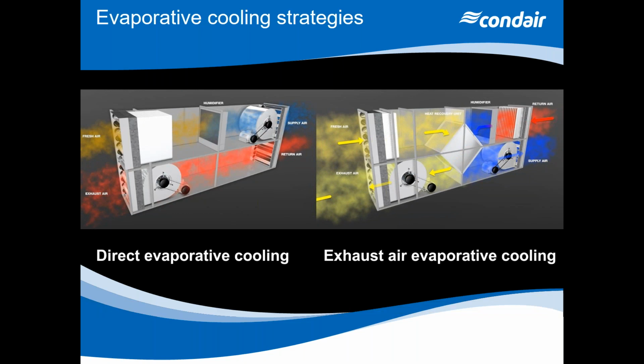So here you can see the evaporative cooling strategies. We mentioned that we've got a change in temperature. Whenever we've got a change in temperature, there are ways that we can utilize that. And in this slide, we can see that there are two ways that we can do it. We can do it either directly, or we can do it with exhaust air evaporative cooling. So when we're doing direct evaporative cooling, all we're doing is taking the fresh air and running it through the filter and then over a humidifier. We're cooling the air, it's evaporatively cooling, and then we send that into the space. And that's pretty straightforward. We then send that humidified air straight into the space and it's cooled down. And then return air comes away from the unit and then goes to exhaust.